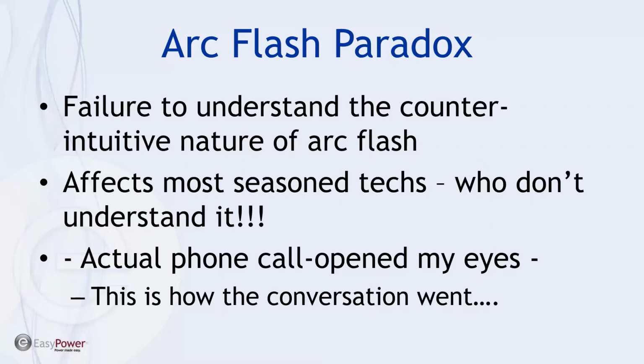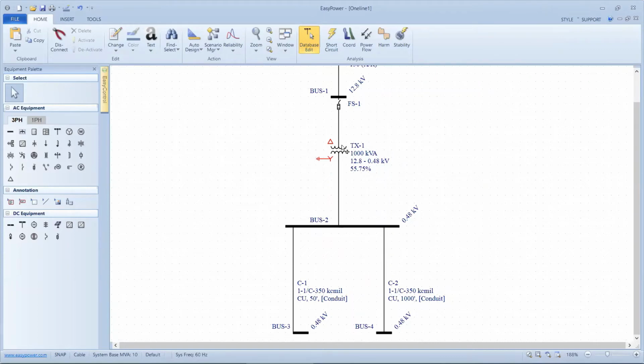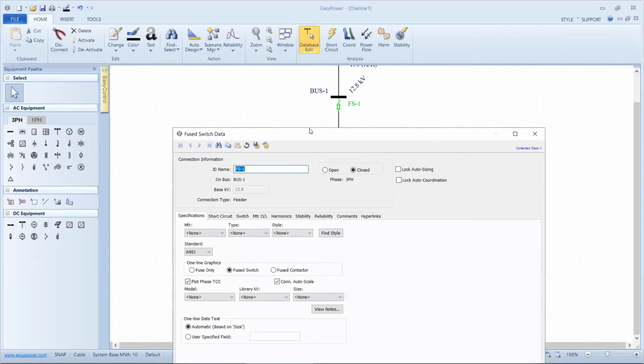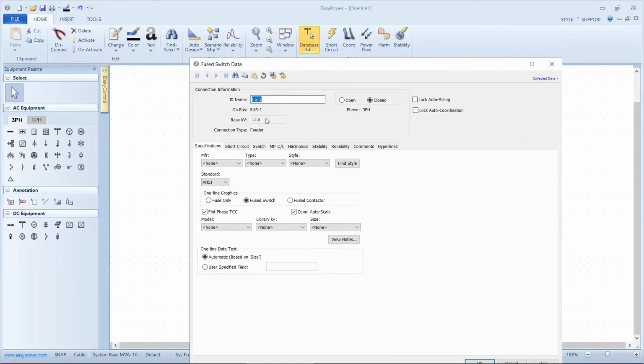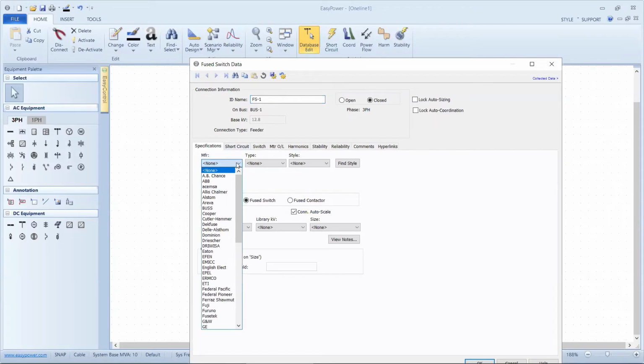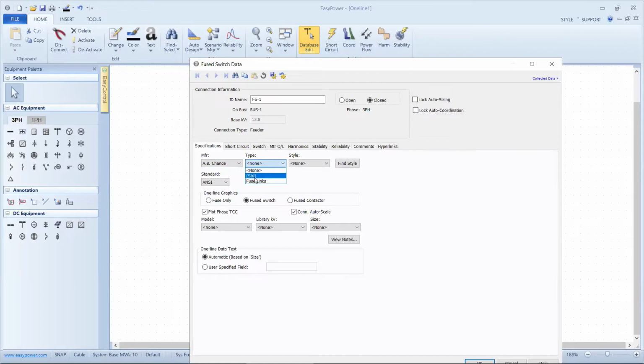So I pick up the fuse switch, open up the dialog box. EasyPower has a device library that has the data for each cable and the transformer. And now we're going to enter the data for the fuse. There's a device library with 40,000 entries in it, and every fuse, relay, and breaker is in that device library. I want to make sure that my one line is connected to the correct data sheet.